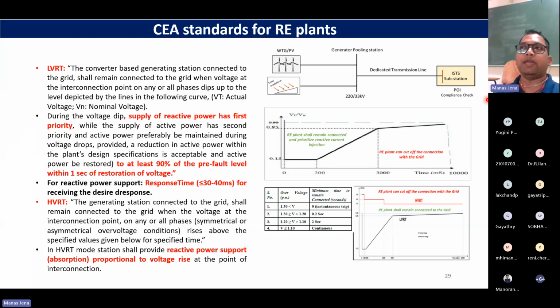Earlier, and even now, many of the conventional plants trip the moment some disturbance happens and they see some RoCoF, which is not desired. Go back to my earlier example of a friend. If there is some issue, you should not trip. You should help your friend. Grid is your friend. How will you help? If there is a fault, low voltage happens. Traditionally, these inverter-based resources, solar, operate using MPPT. You say that whatever maximum power I am generating now, I should dump it to the grid. But during a fault you should not do this. Fault means you have a low voltage scenario, right? You should provide VAR support to the grid.